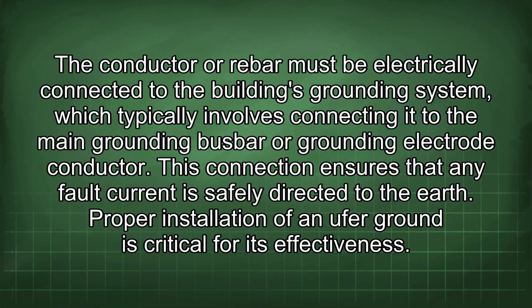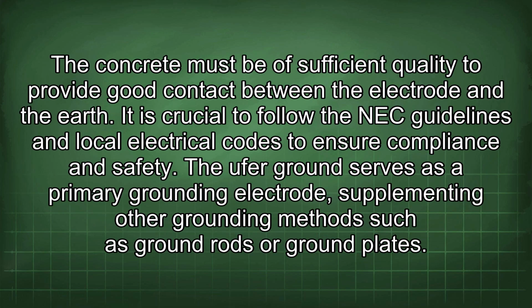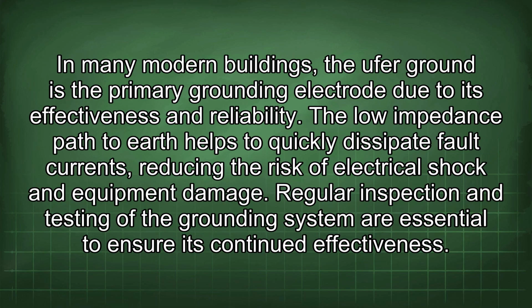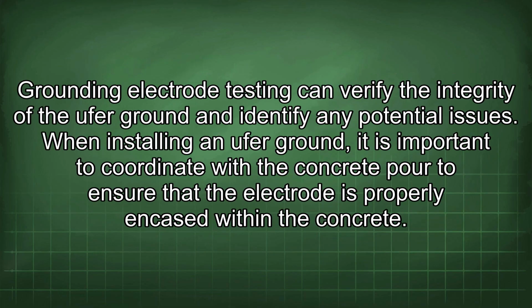Proper installation of a Ufer ground is critical for its effectiveness. The concrete must be of sufficient quality to provide good contact between the electrode and the earth. It is crucial to follow the NEC guidelines and local electrical codes to ensure compliance and safety. The Ufer ground serves as a primary grounding electrode, supplementing other grounding methods such as ground rods or ground plates. In many modern buildings, the Ufer ground is the primary grounding electrode due to its effectiveness and reliability. The low-impedance path to earth helps to quickly dissipate fault currents, reducing the risk of electrical shock and equipment damage. Regular inspection and testing of the grounding system are essential to ensure its continued effectiveness. Grounding electrode testing can verify the integrity of the Ufer ground and identify any potential issues.